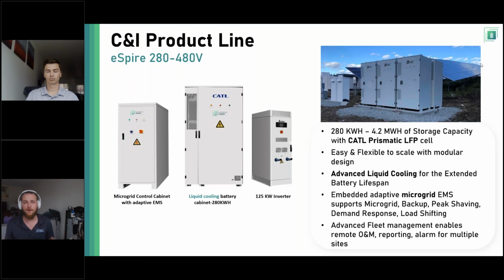This first product is called the Espire 280, standing for 280 kilowatt hours of energy storage, which is the battery cabinet in the center. On the right is a 125 kW inverter. We can put 5 of those inverters together to get 625 kW of 480 volt power, and 3 batteries to each of those 5 inverters for 15 total battery cabinets to a single feeder. That's roughly 4.2 megawatt hours of energy storage.